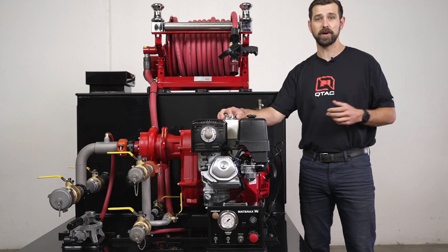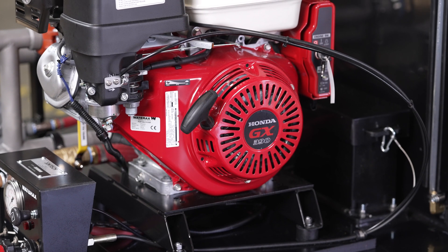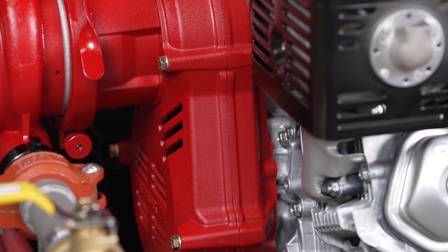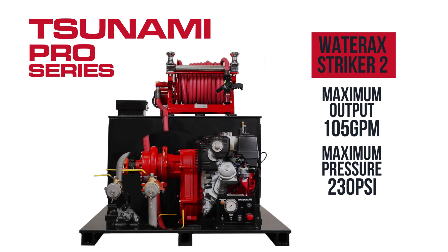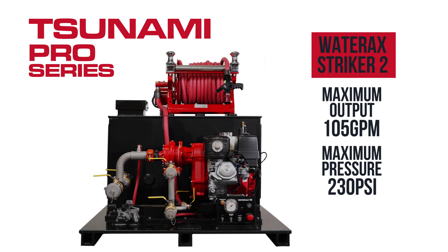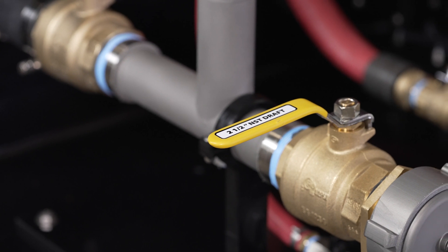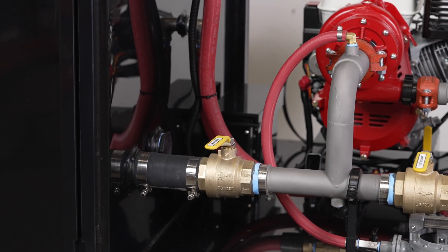This skid is shown here with an electric start Honda GX390 13 horsepower engine with backup pull start and a low oil sensor, mated up to the WaterAx Striker 2 pump. This pump has a max output of 105 GPM and a max pressure of 230 PSI. This pump comes with a 2.5-inch NST gated draft suction and a 2.5-inch NST gated tank to pump.